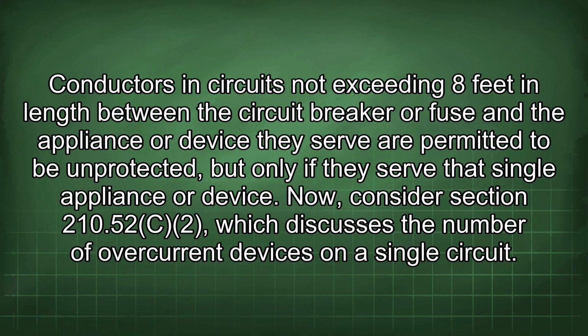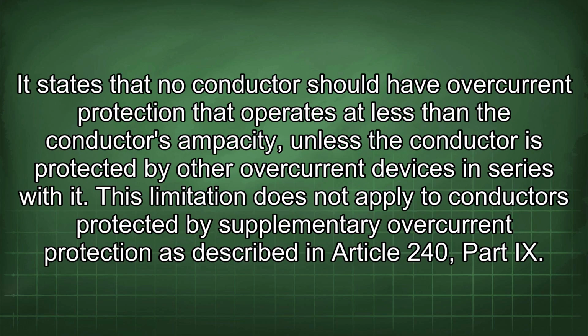Now consider Section 210.52(c)(2), which discusses the number of overcurrent devices on a single circuit. It states that no conductor should have overcurrent protection that operates at less than the conductor's ampacity unless the conductor is protected by other overcurrent devices in series with it. This limitation does not apply to conductors protected by supplementary overcurrent protection as described in Article 240, Part IX.